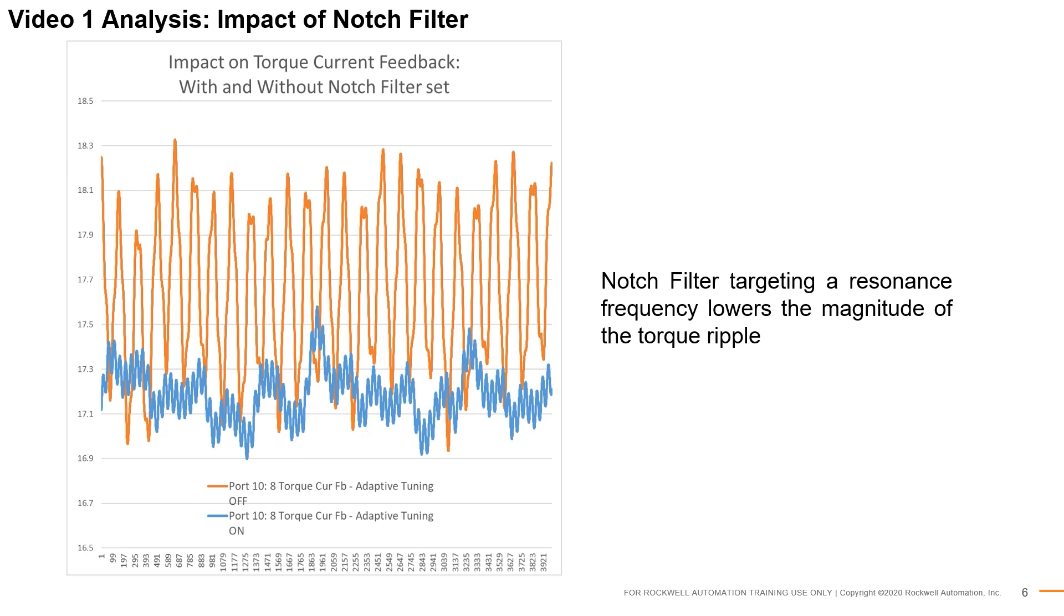We can observe that when adaptive tuning sets a notch filter at the injection frequency, the magnitude of the ripple on the torque current feedback is reduced. This reduction is observable in the blue trace. This concludes the notch filter setting demonstration.